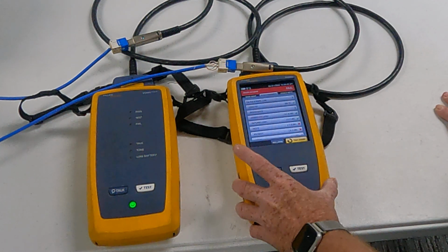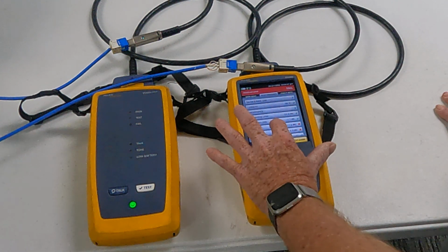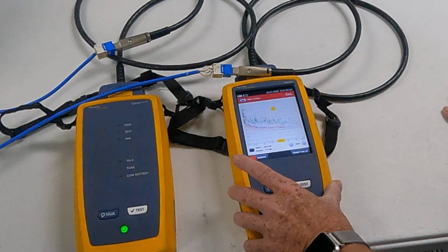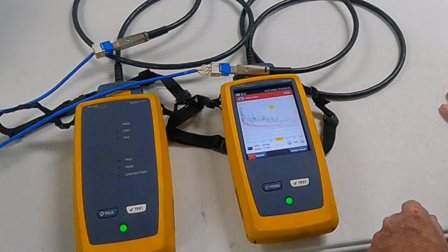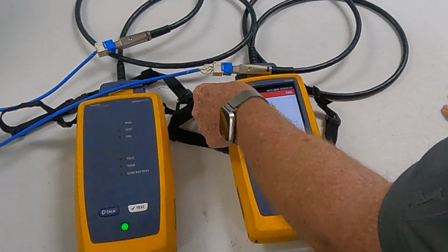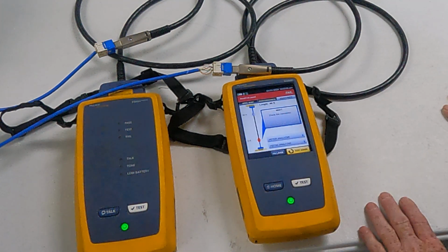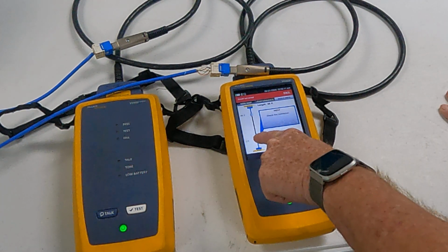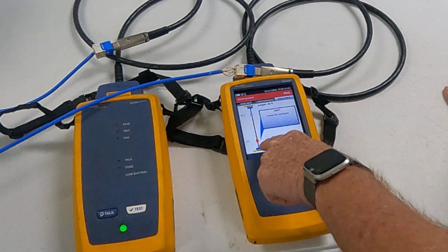Now, it's failing on near end crosstalk and power sum crosstalk. So we'll go into the next on it. Okay. And so it's giving you the reading. Now it says next at the main, so we know it's at the main, and the worst pair looks like the green. But we can go back here and you can just go to the fault info and it says check the connector. So it's showing the connector on this side. So that's the main, this is the main side.